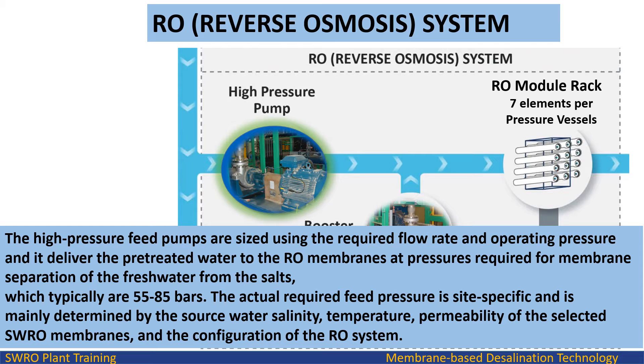The required pressures typically are 55 to 85 bars. The actual required feed pressure is site-specific and is mainly determined by the source water salinity, temperature, permeability of the selected SWRO membranes, and the configuration of the RO system.